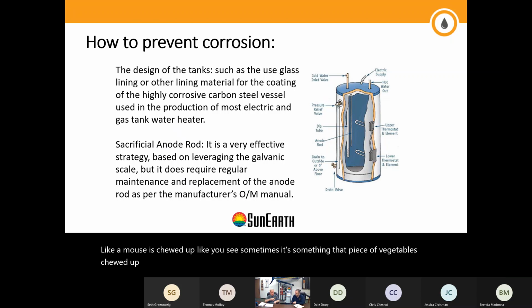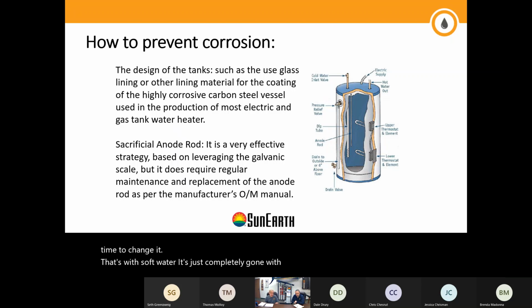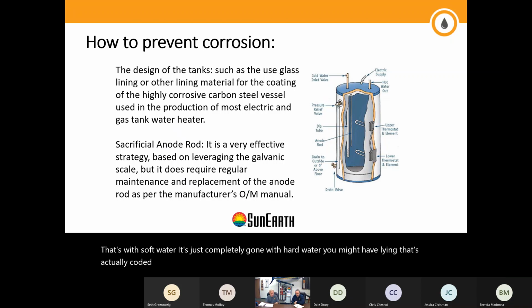It's chewed up in various places. When about half or more is gone, it's time to change it. That's with soft water, where it's just completely gone. With hard water, you may have lime that has actually coated the anode. The lime acts as an insulator, just as it does for thermal transfer. So you would clean off the anode with a wire brush and replace it.